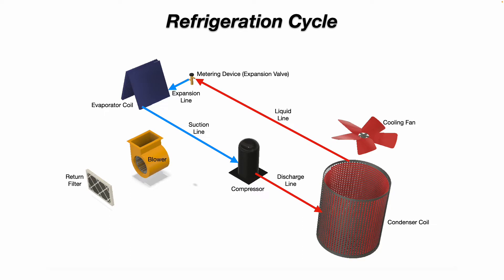The condenser cooling fan is going to dissipate that heat energy out of the condenser to the open atmosphere. The refrigerant is going to change state about halfway through the inside of the condenser coil, and then it leaves as a high-pressure liquid on the liquid line going into the metering device or expansion valve, where it expands and quickly reduces in pressure and temperature.